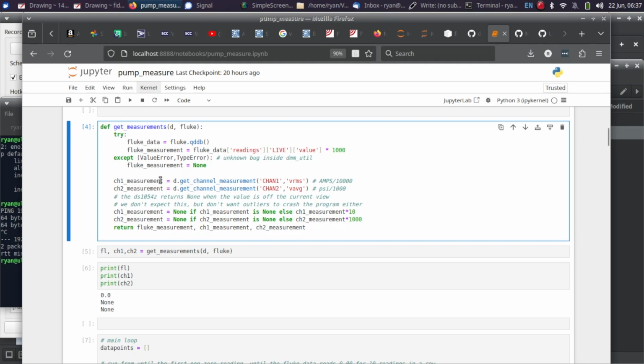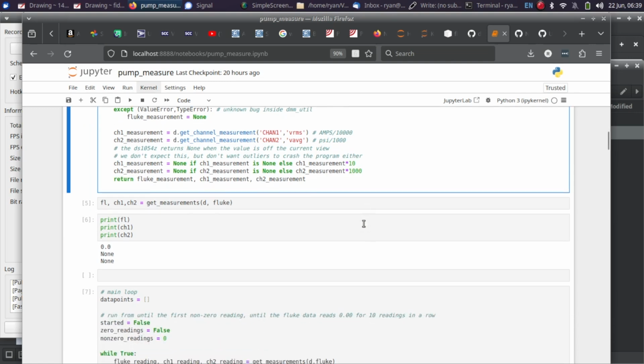And then the Rigol readings are a little more robust. It will return none if the readings are out of range of what is currently on the screen. So if the scale is not set correctly for channel 1 or channel 2, one of these will come back as none. Channel 1 is the current clamp. Channel 2 is the pressure transducer. So I'm passing none out if the measurement is none. Otherwise, I am doing the math here to multiply it into the values. The current clamp is 1 millivolt per 10 milliamps of current, and then the pressure transducer is 1 millivolt is 1 psi. So that's just getting straight multiplied by 1,000.